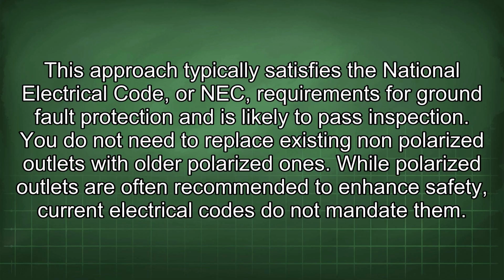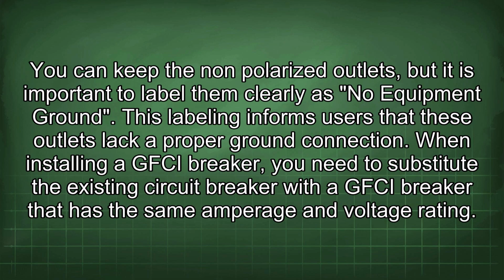While polarized outlets are often recommended to enhance safety, current electrical codes do not mandate them. You can keep the non-polarized outlets, but it is important to label them clearly as no equipment ground. This labeling informs users that these outlets lack a proper ground connection. When installing a GFCI breaker, you need to substitute the existing circuit breaker with a GFCI breaker that has the same amperage and voltage rating.